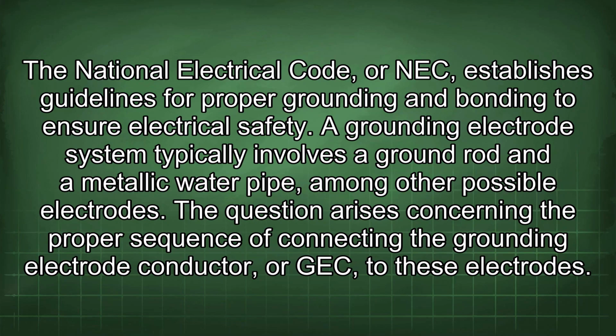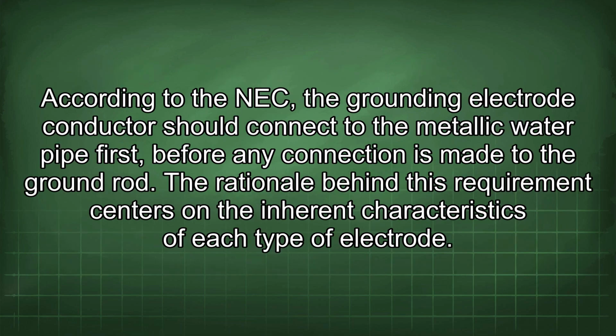The National Electrical Code, or NEC, establishes guidelines for proper grounding and bonding to ensure electrical safety. A grounding electrode system typically involves a ground rod and a metallic water pipe, among other possible electrodes. The question arises concerning the proper sequence of connecting the grounding electrode conductor, or GEC, to these electrodes. According to the NEC, the grounding electrode conductor should connect to the metallic water pipe first, before any connection is made to the ground rod.